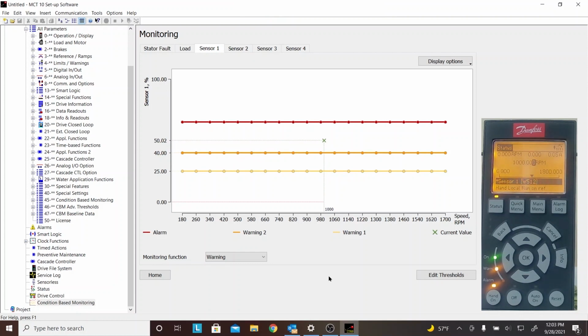And over time, as this degrades, watch the sensor on the keypad, you'll go into S2 warning, which means you're in your second warning now. So now things are getting worse. Now we need to really do something, because if we don't, we're going to eventually end up here, over an alarm status. If we have the alarm chosen in the monitoring function, we're going to trip the drive and shut everything down. But if we don't, we're just going to know we're there. So even if we plug in, we're going to be able to see it, but we're not going to trip the drive. So that's great.